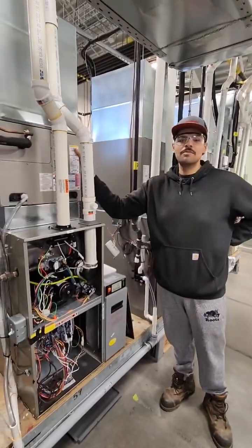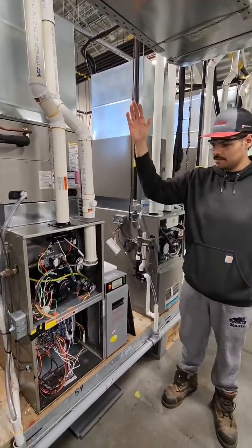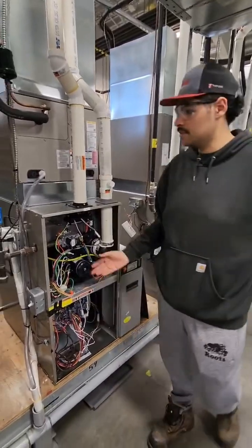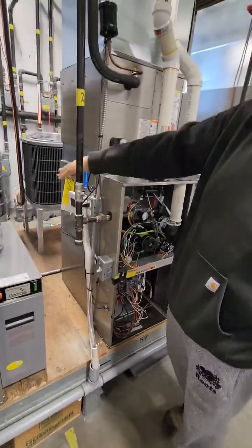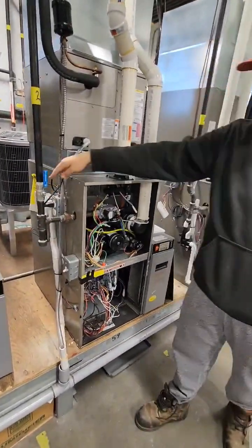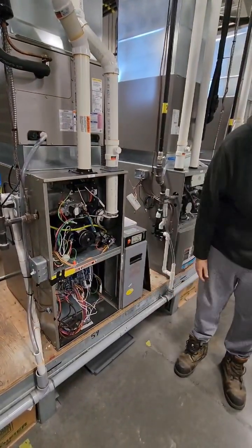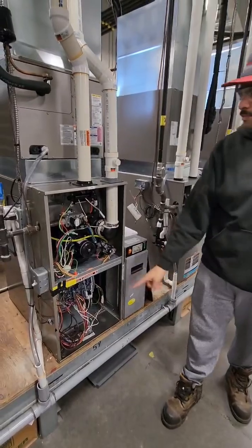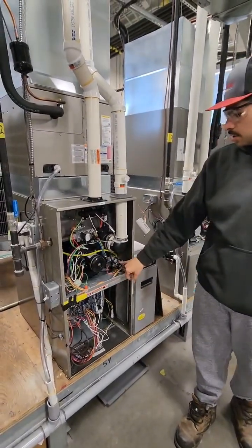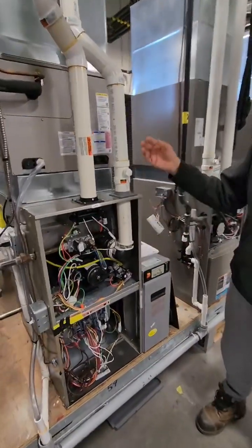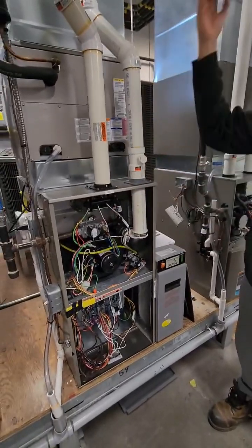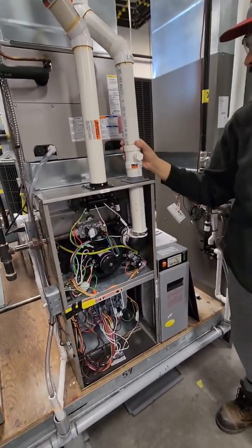Alrighty, so today we'll be talking about the mid-efficiency furnace. I'll just be going through the process that the furnace runs on. So you first start off by calling for heat. Your thermostat will send power through all the safety switches, which then activates your R and W contacts on your control board, which then powers your inducer motor, which closes your pressure switch, which allows the venting to start. So we start drafting out of these pipes here.